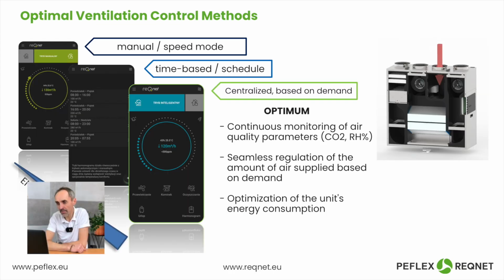In our opinion, the optimal control is the one based on air quality measurements, because the two previous solutions, manual control, like adjusting the speed yourself, or time-based control according to schedules, have certain limitations that affect the air quality. So, we might switch to a higher speed too late, and at that point, the concentration of carbon dioxide in the building increases, or on the other hand, we might also turn off that speed too late, which generates additional costs due to higher energy consumption by the fans. And, a sort of halfway solution is this time-based control, meaning using schedules.